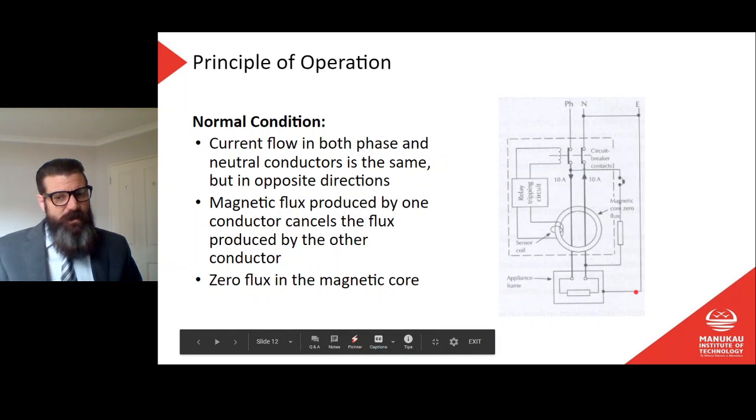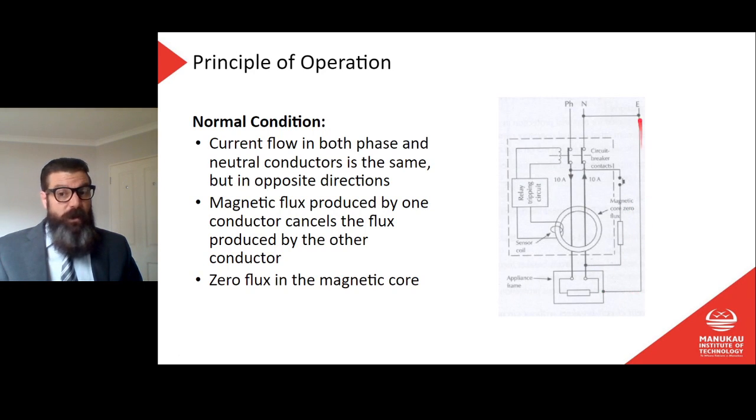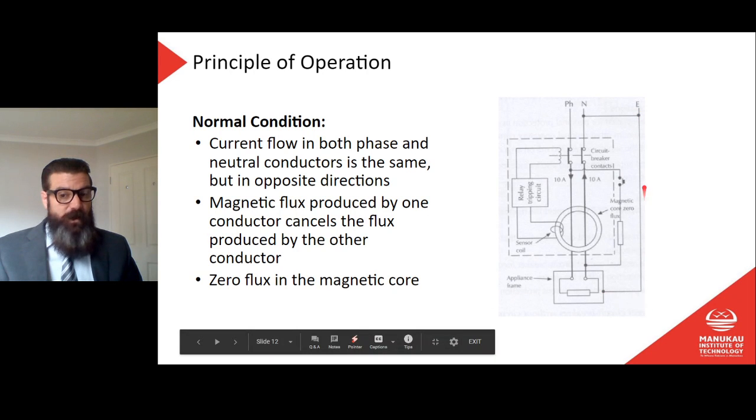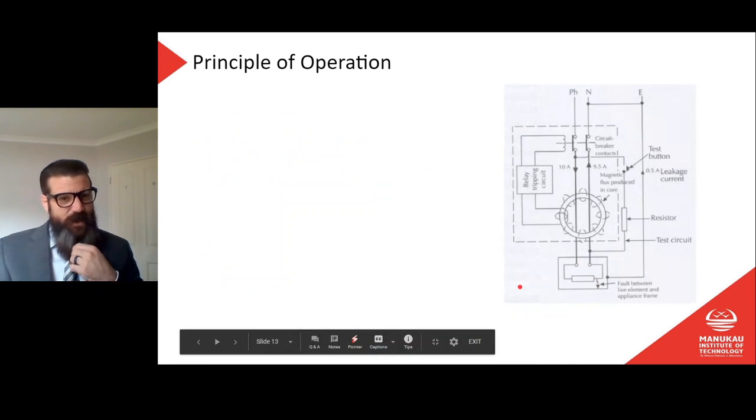Note that it's not testing whether the earth back to the switchboard is any good. All it does is test that the device actually operates internally. So it's not a foolproof test.